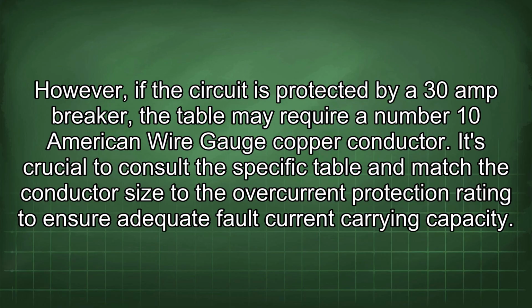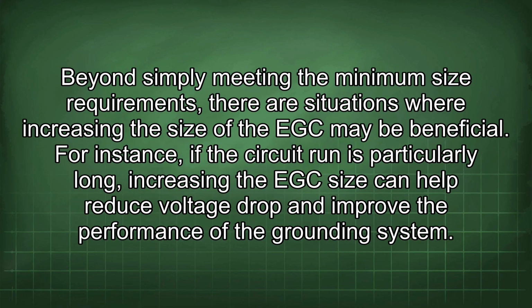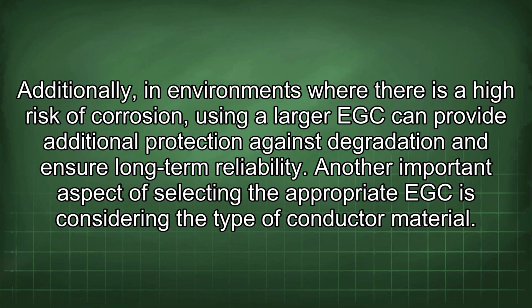Beyond simply meeting the minimum size requirements, there are situations where increasing the size of the EGC may be beneficial. For instance, if the circuit run is particularly long, increasing the EGC size can help reduce voltage drop and improve the performance of the grounding system. Additionally, in environments where there is a high risk of corrosion, using a larger EGC can provide additional protection against degradation and ensure long-term reliability.